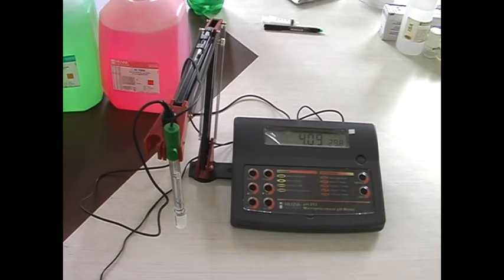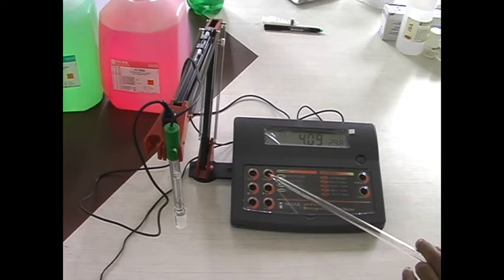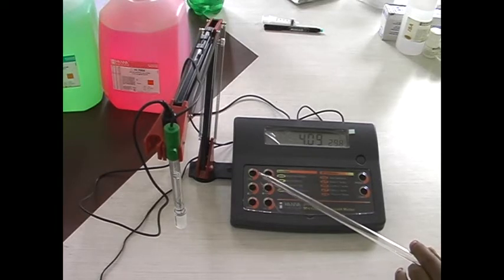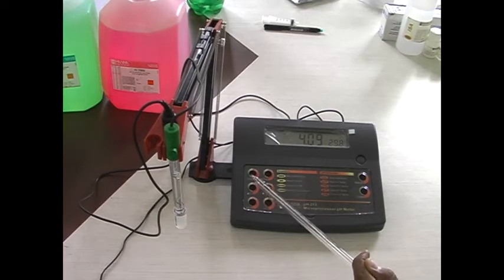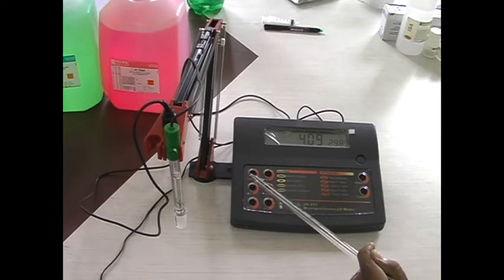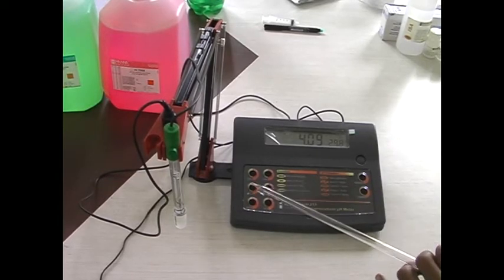Now we are going to see the functional description of the PH213. Basically the PH213 front panel includes the following soft keys. This is a large LCD display. You can see the pH measurement on the primary display and the temperature reading on the secondary display. This is a CFM key. This is the key to confirm the calibration values. This is a CAL key, or you can say calibration key, to enter or exit calibration mode. This is a down arrow key to manually decrease temperature or to select the pH buffer.